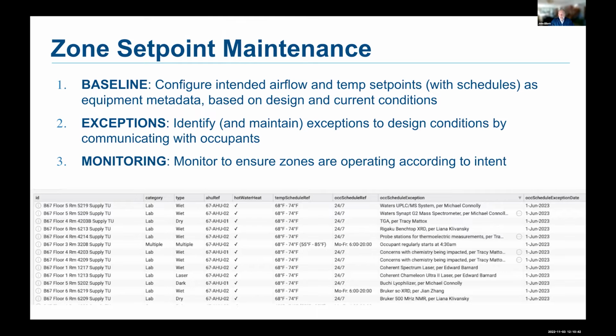Then we recognize that some zones have special equipment that may need special space conditioning requirements. So we're doing a manual process where we're communicating with the occupants through building managers, and we're identifying exceptions to those design conditions, and then we're maintaining that. And those actually come into the SkySpark system as well. So here's like a list of various exceptions. And then we can monitor and ensure that the zone operation is actually operating according to intent.